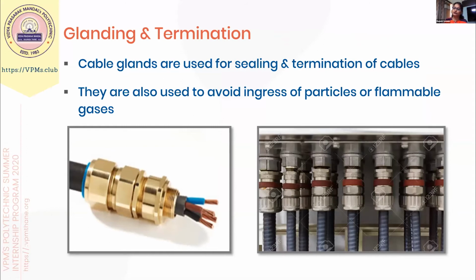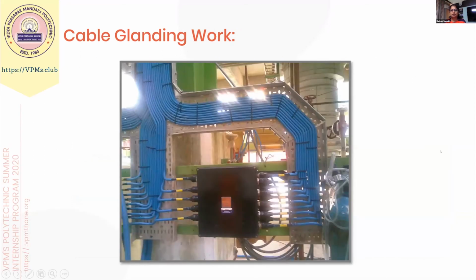They are also used to avoid ingress of particles or flammable gases. Like if the cable is terminated in a junction box, it will avoid any unwanted particle or flammable gas entering the panel or junction box. So this is the cable gland, and you can call this glanding. This is also glanding work. You can see the JB, tray, and the cables and the glands.